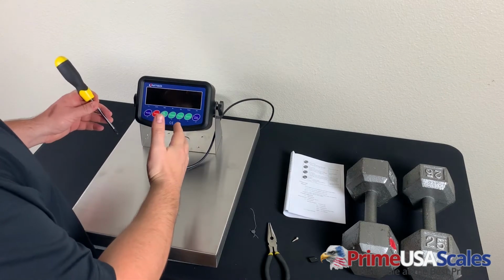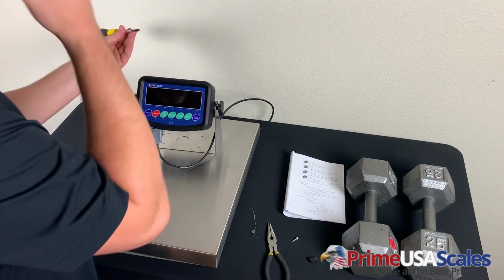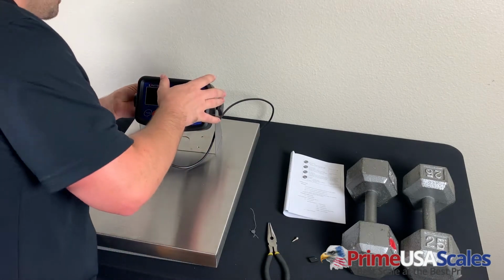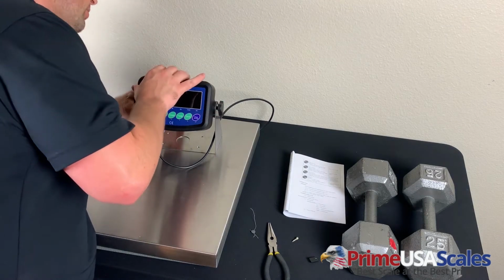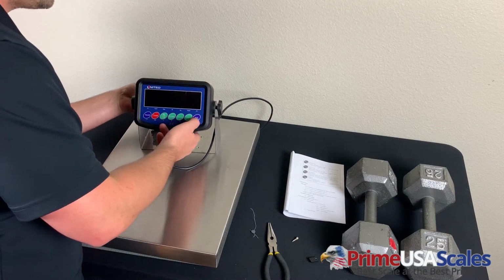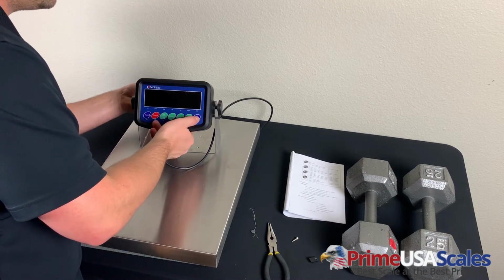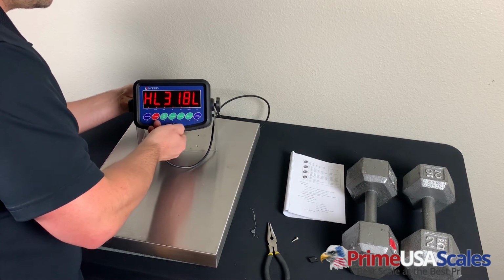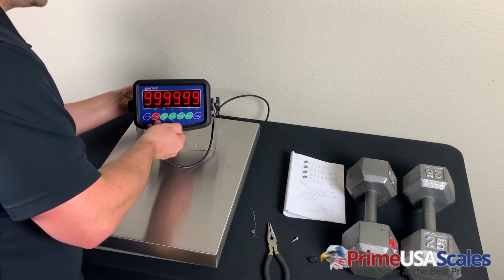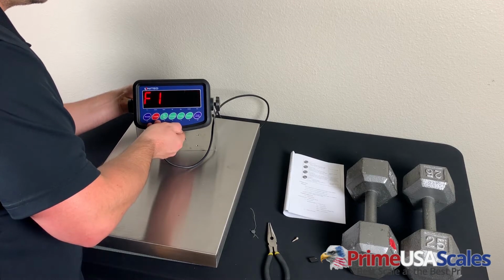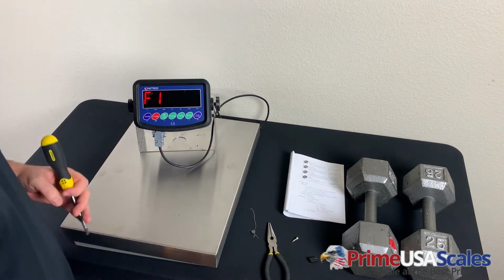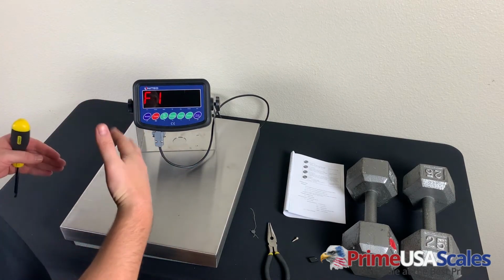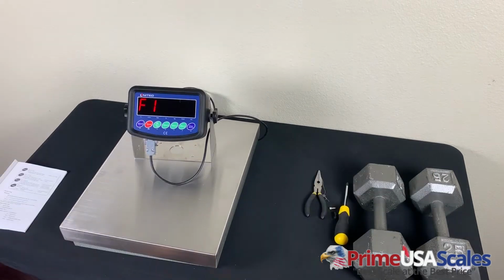Now to put the scale into calibration mode, what we need to do is take our screwdriver and apply pressure to that calibration switch, and we're going to hold that in place. Then we're going to hit the on-off key. We're going to continue to hold that calibration switch until it goes through the countdown phase, and it'll set us to F1. So this is the first start of the calibration.